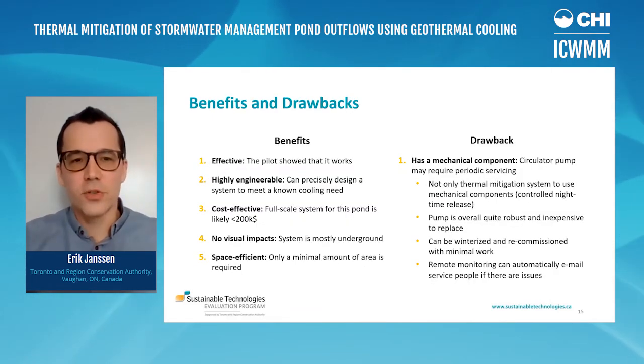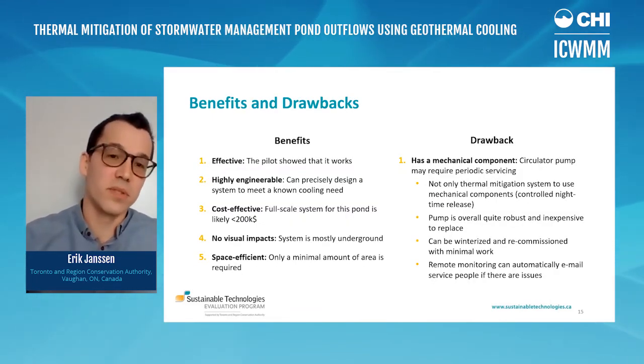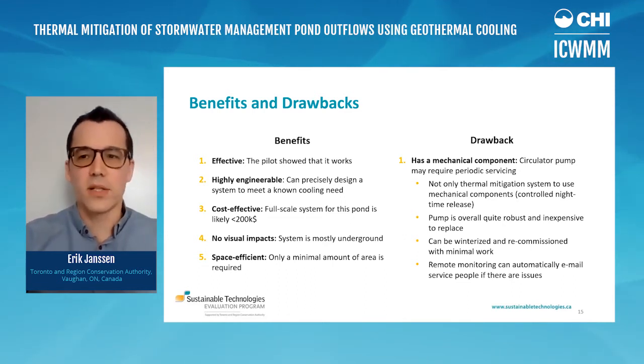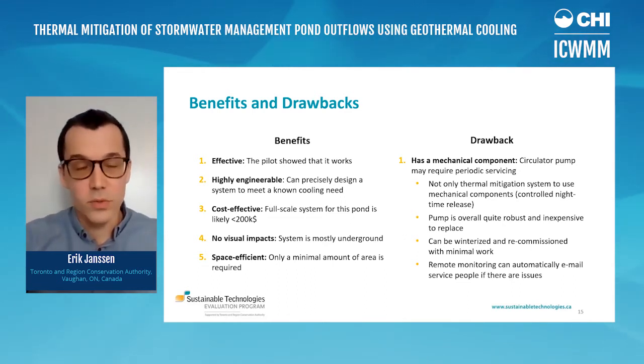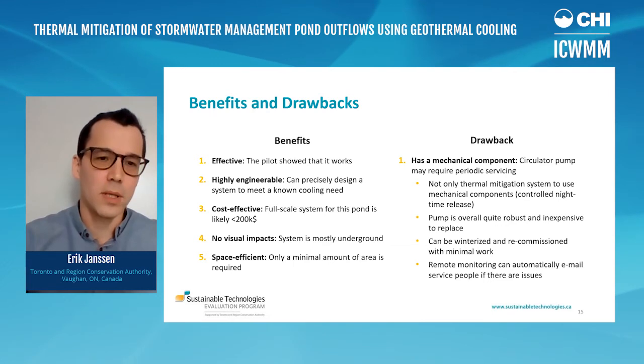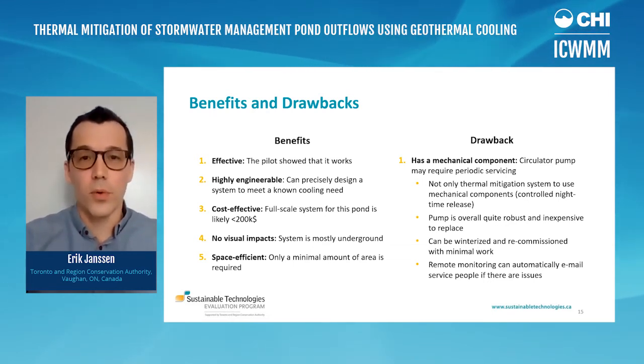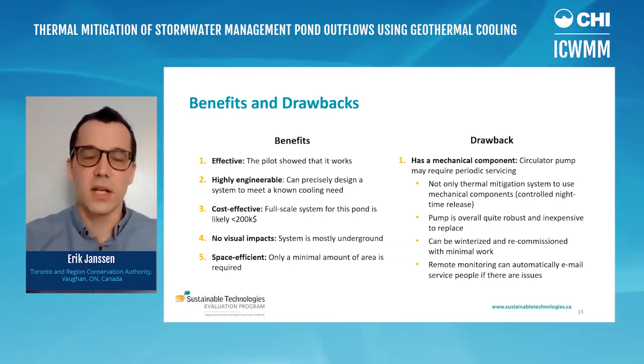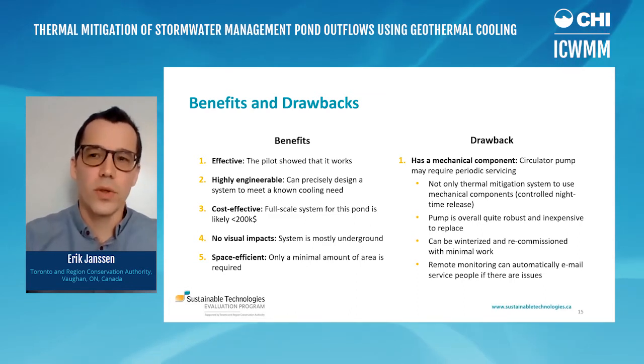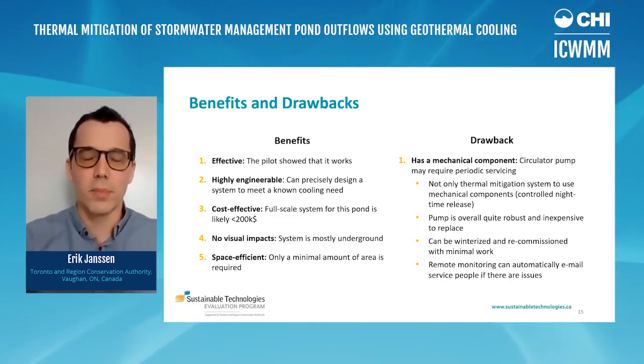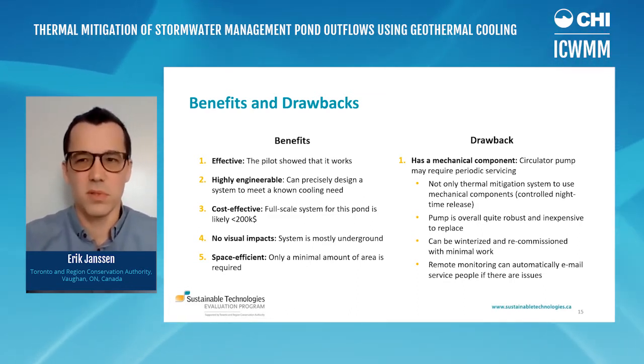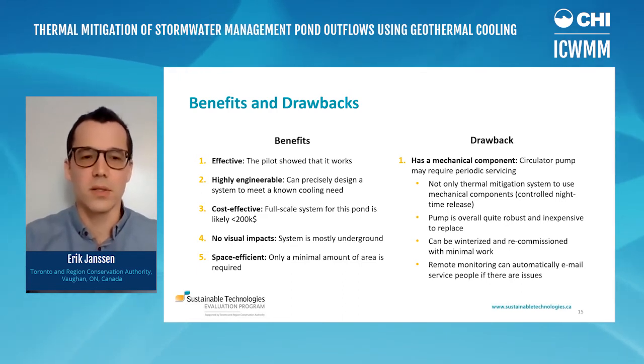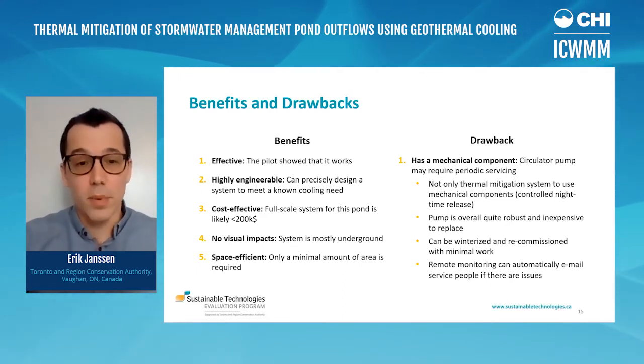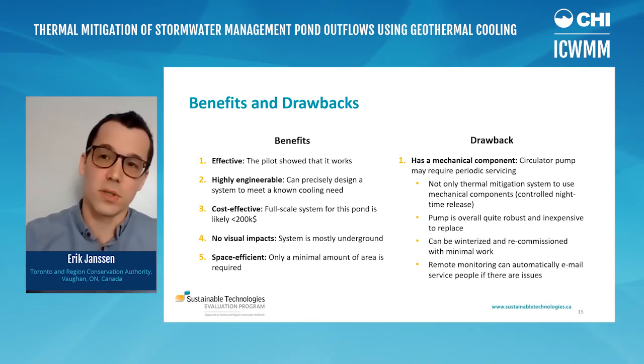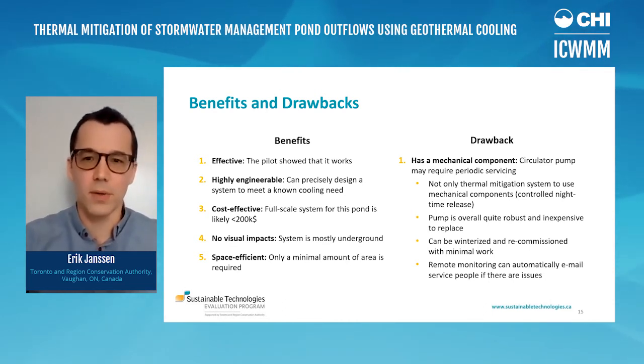In terms of benefits and drawbacks, we show that the system's effective, it works. We can describe it with relatively simple equations, which is nice, makes it highly engineerable. It's cost effective. The boreholes themselves are on the scale of $15,000 each. We think 4 to 6 would be required for a pond of this size. So the full scale system is maybe $100,000 to $200,000. There's no visual impacts on the pond, which is nice. And it's also space efficient because most of the work is happening underground.